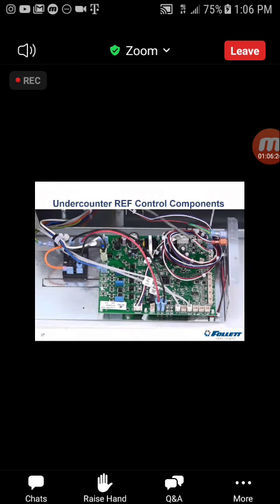Inside the electrical box, we can see the electrical control board on the right and the control relay on the left. On the control board on the bottom, the two probes are connected, P1 and P3. The center connection for P2 is open. If this was a freezer, the defrost termination probe would be connected here. The relay has a black and a red wire going from the control board to the coil of the relay. The relay is polarity sensitive. When replacing the relay, it's important to remember that the red wire has to be connected between the R1A terminal on the control board and the number 3 terminal on the relay. The black wire goes from the R1B terminal on the control board to the number 4 terminal on the relay.